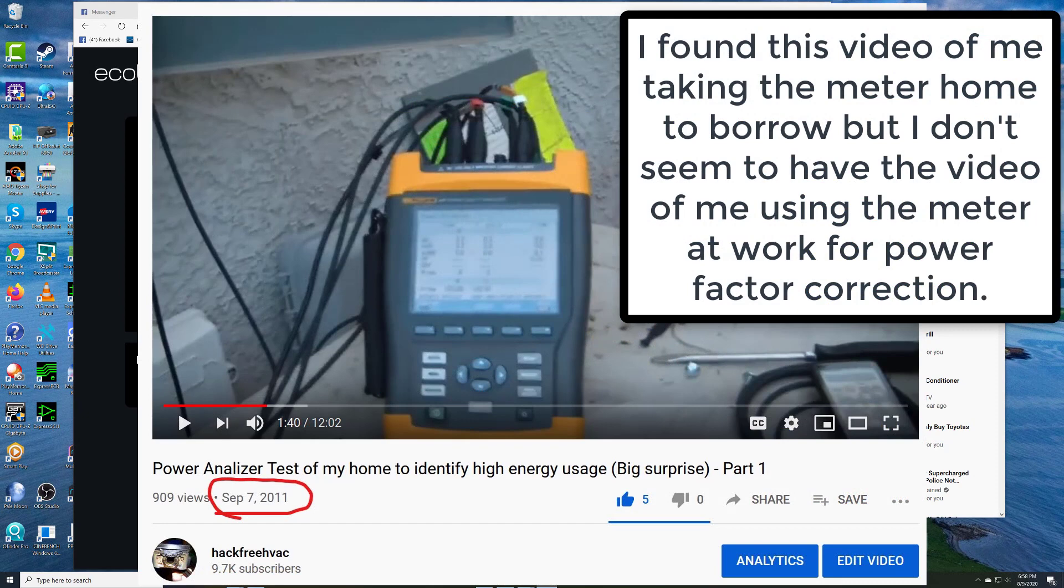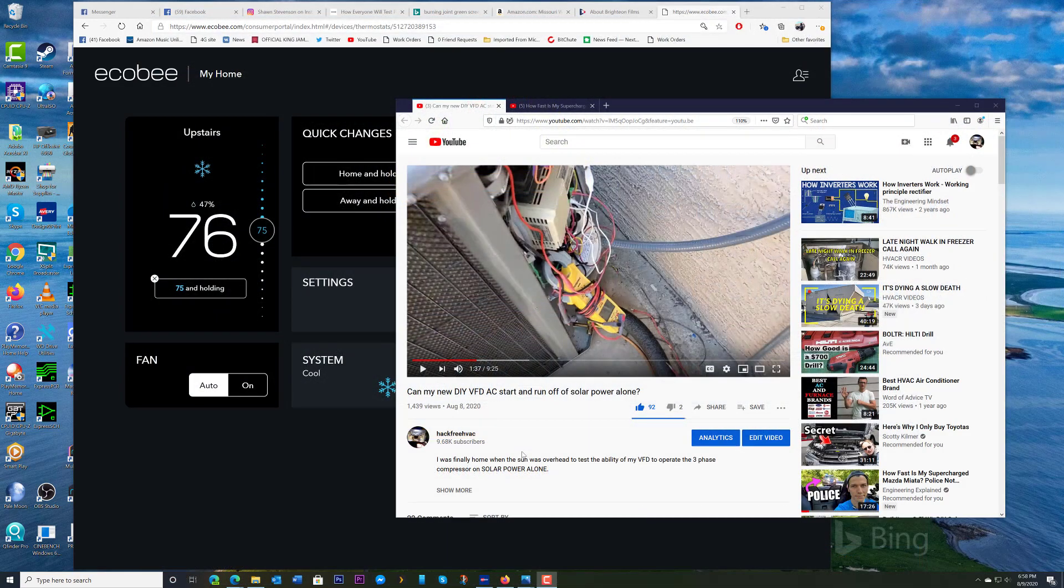It showed you how the voltage and the current would be out of phase, out of relationship when the power factor was way off. We corrected that with power factor correcting capacitors that you just bolted in parallel to the windings of the motor. And we kind of tightened that up.